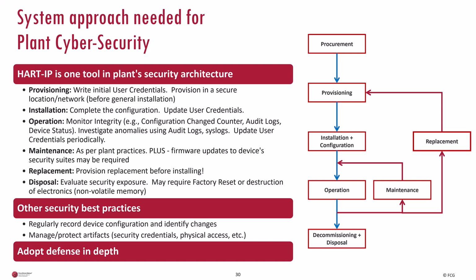During operation, you're going to monitor the integrity of the devices. That includes configuration change counters, device status, maybe looking at the audit logs. Any anomalies you need to investigate during that time. Maintenance is usual plant practices. However, you must also consider whether firmware upgrades are going to be needed during that time because of security vulnerabilities or new cybersecurity suites. Replacement is sort of like going back and starting over with the provisioning and getting those credentials in there and then configuring the device.